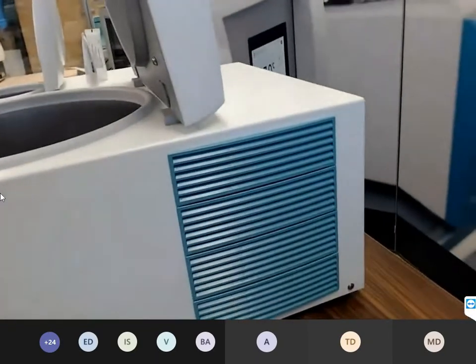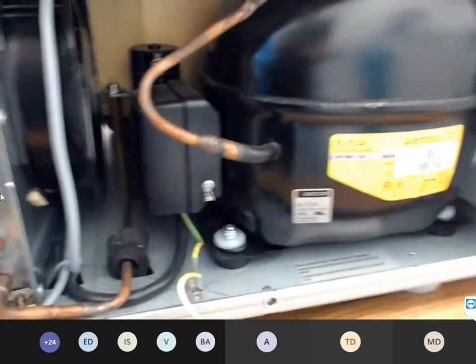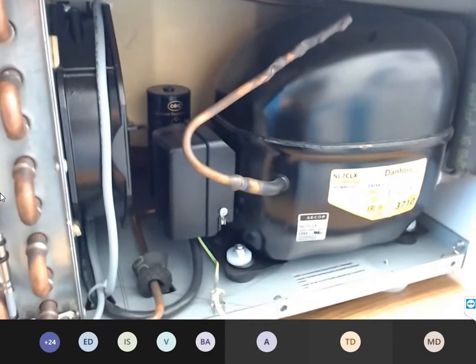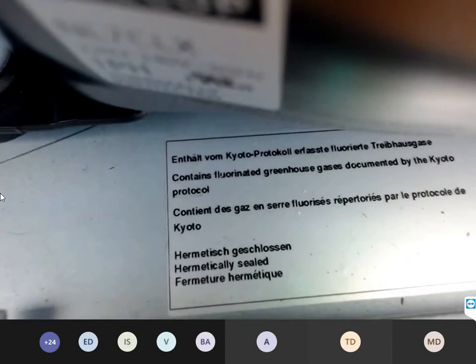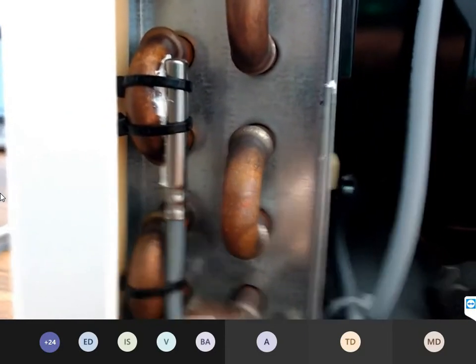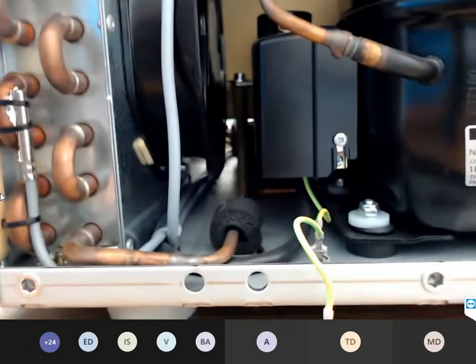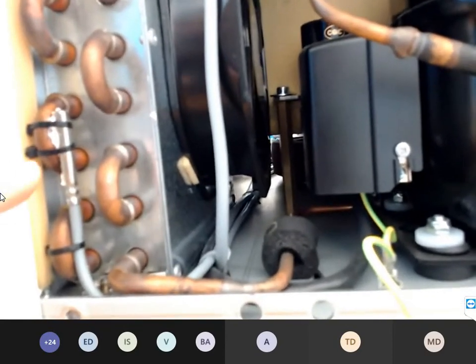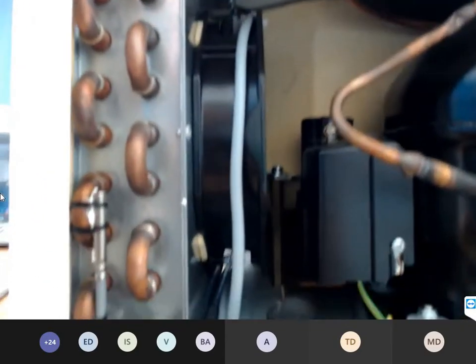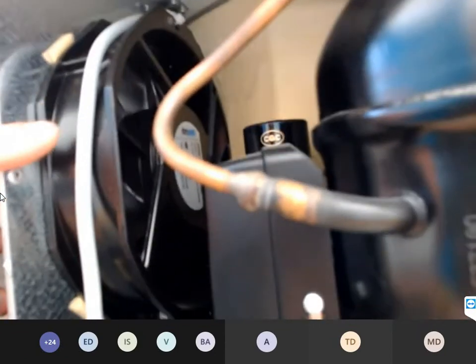And now we go to the back side. The technical design is the same. We have here the compressor and the nameplate. On the nameplate, you will find all relevant data. Very important: the temperature sensor for the condenser. If you replace this sensor, please fix it again in exactly this position. The position is very important. This black one is the fan of the condenser. We have here the condenser and the starting relay for the compressor.